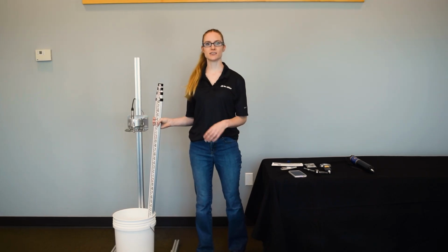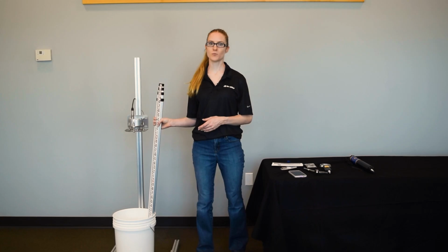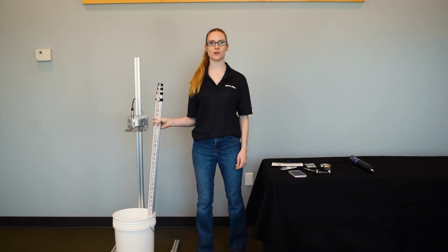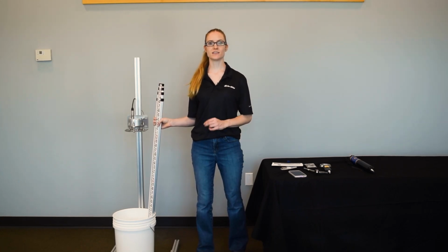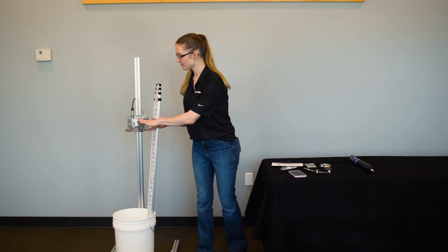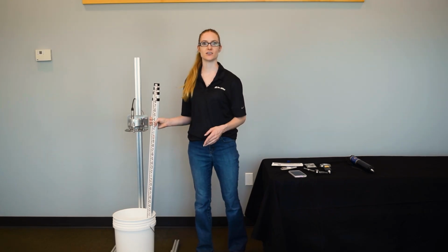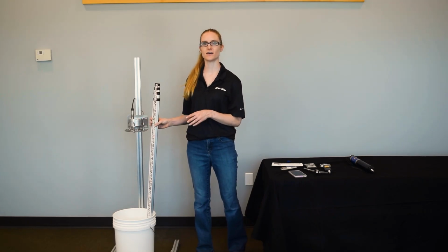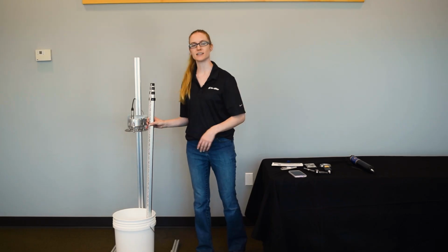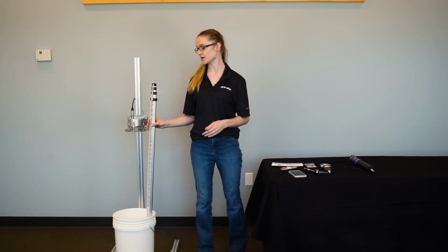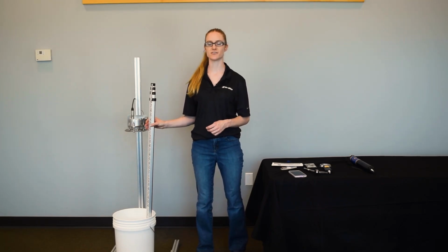Use a staff gauge, level tape, or other surveying tool to help you find these measurements for your specific deployment site. One thing that's important to note is to make sure that your instrument is level in its final installation location before entering water level references. You'll need to re-enter your water level references in VuSitu if the instrument is moved or tilted after setup.